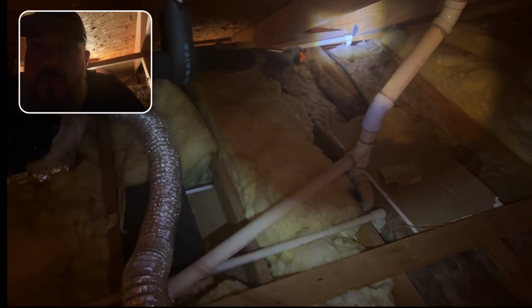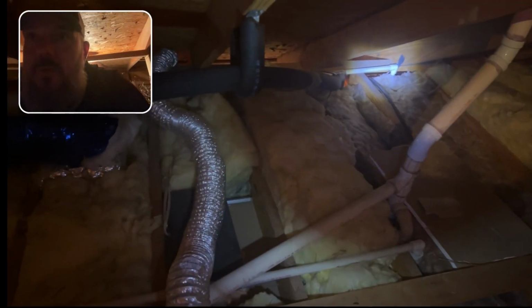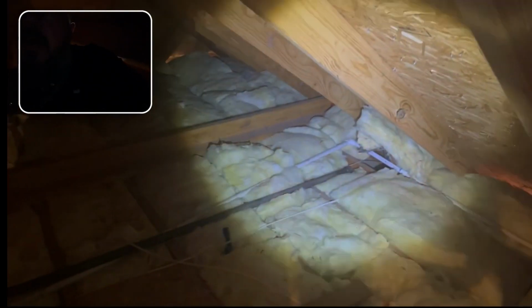That white PVC pipe that you see back there in the corner is the emergency overflow for the AC system. It runs all the way across about 20 feet or so. And then notice how high off of that ceiling joist it is. It's about 3 or 4 inches high. It runs this way, and it's touching the ceiling joist. I don't know if y'all can see that or not. So it's actually up pitched, and it goes that way, and it gets tied into the emergency overflow on that system.